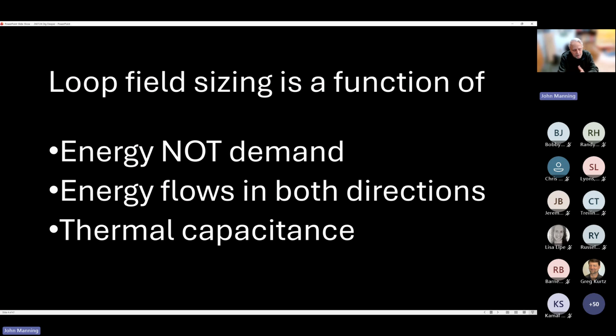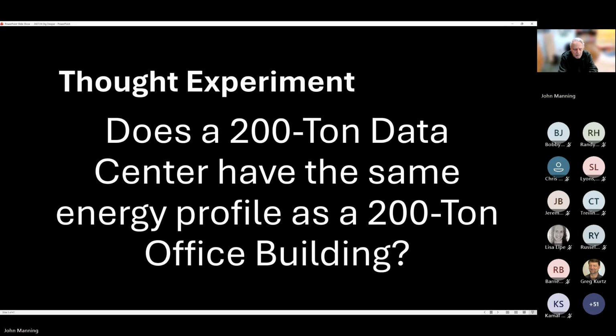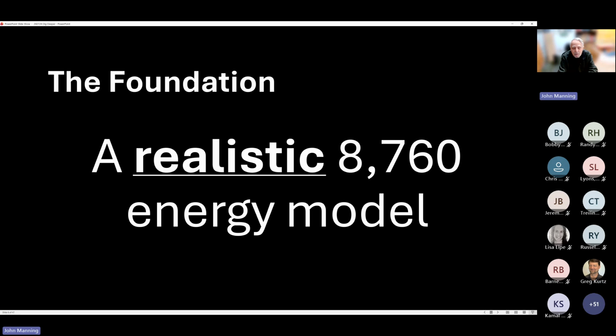Loop field sizing, just to reiterate what I think we all know, is a function of energy, not demand. Energy flows in both directions, which is kind of unique for most heat exchangers. Thermal capacitance is another aspect of geothermal that's different than, say, a cooling tower. I pose a thought experiment: does a 200-ton data center have the same energy profile as a 200-ton office building? If you've been in this industry at all, you know they're totally different. So the foundation of any geothermal system is understanding that energy model over time, and it has to be realistic.